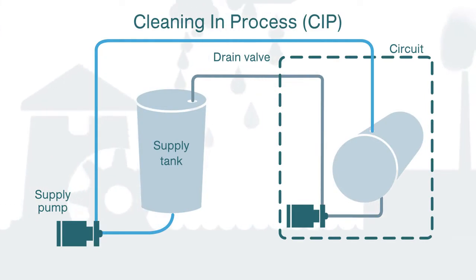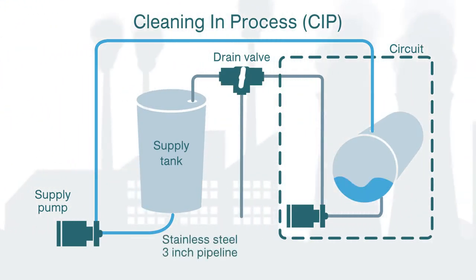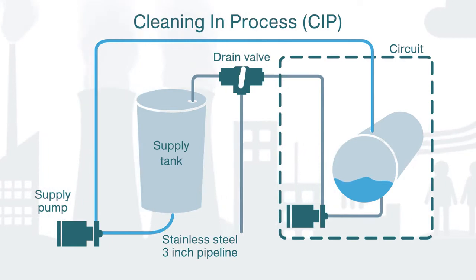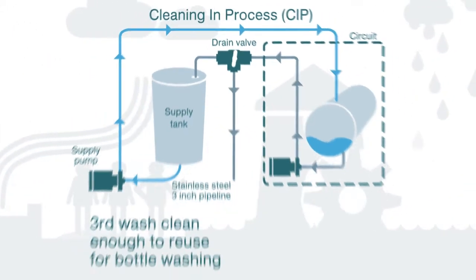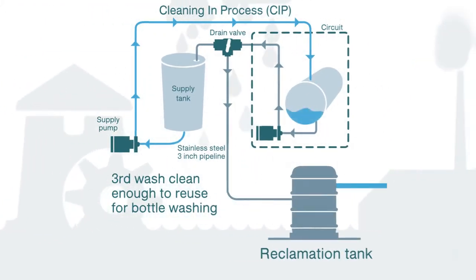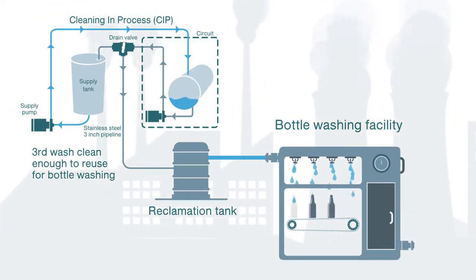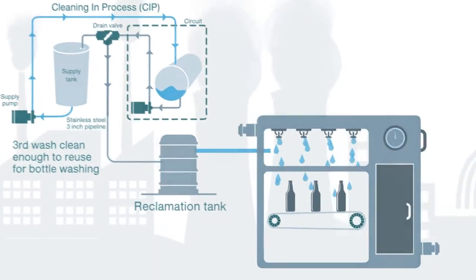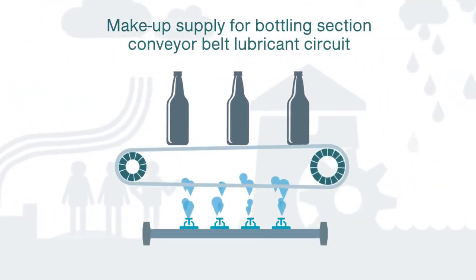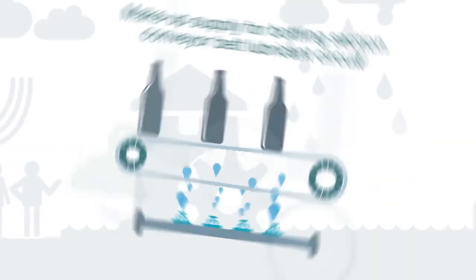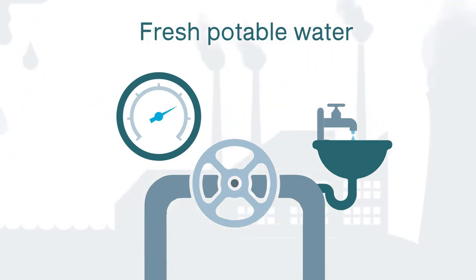A 40-metre stainless steel 3-inch pipeline was installed from the cleaning-in-process (CIP) rinse tanks to divert water to a reclamation tank, to serve as a top-up supply to the bottle washing facility and as a make-up supply for the bottling section conveyor belt lubricant circuit. This resulted in offsetting the need for fresh, potable water for these applications.